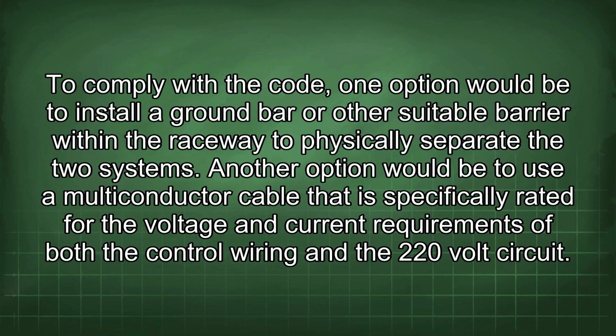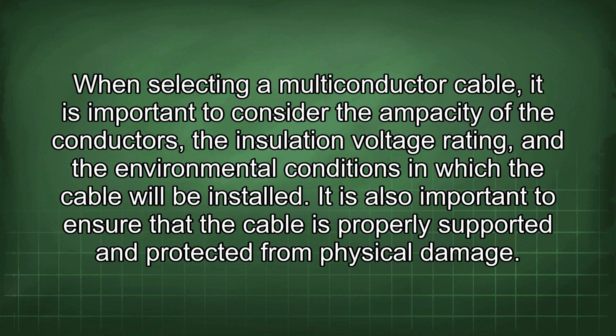Another option would be to use a multi-conductor cable that is specifically rated for the voltage and current requirements of both the control wiring and the 220-volt circuit. When selecting a multi-conductor cable, it is important to consider the ampacity of the conductors, the insulation voltage rating, and the environmental conditions in which the cable will be installed.